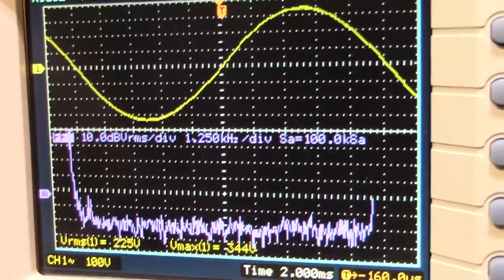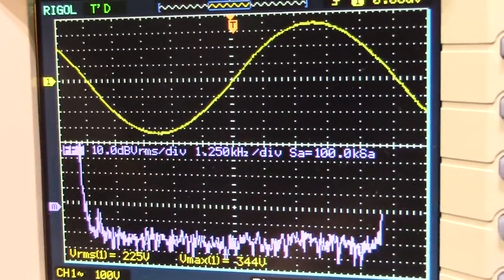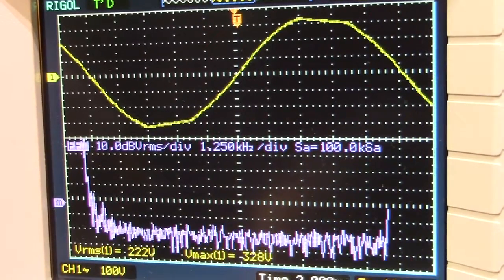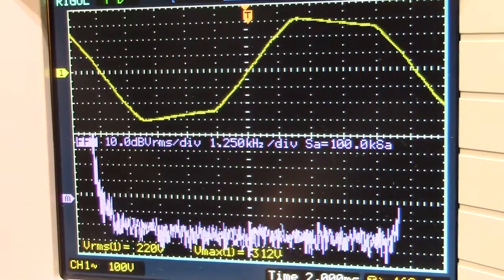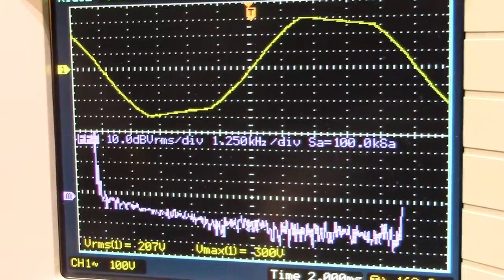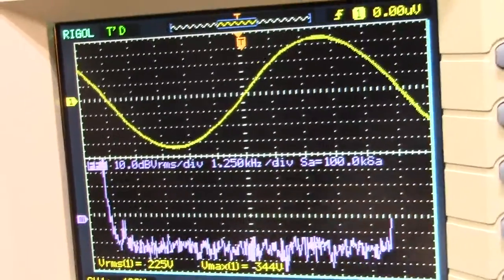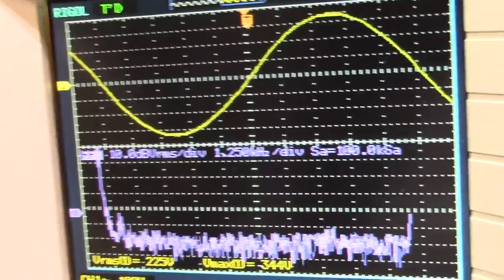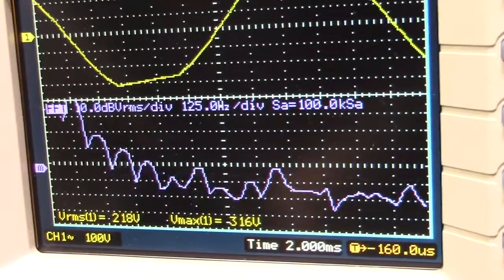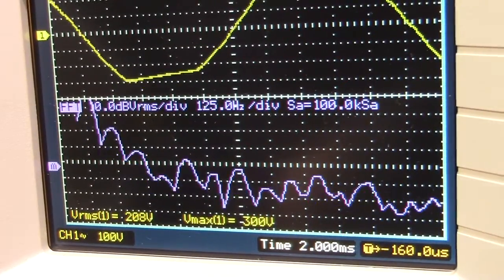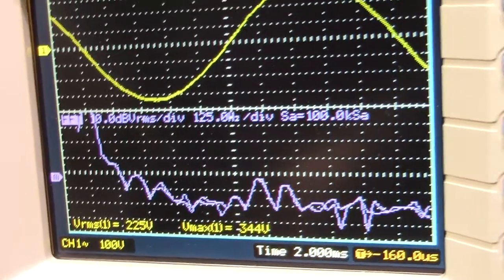Now, if I just overload the unit slightly by flipping this heater into high, we can coax the UPS into clipping, and we can, if we zoom in a bit, even see the clipping harmonics starting to grow there. So I'll turn this off now.